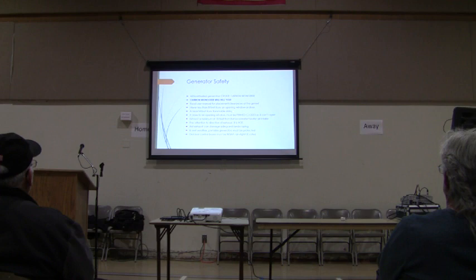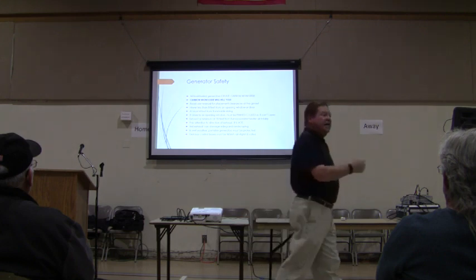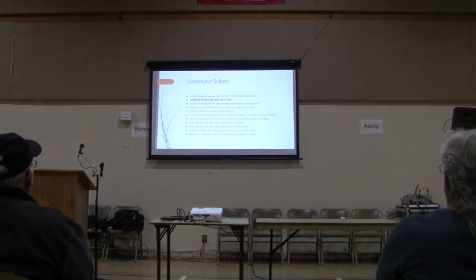Exhaust a minimum of 10 feet from furnace and water heater air intakes. And I would say 10 feet from an outdoor unit as well, because the combustion byproducts will destroy the wiring in an outdoor condensing unit. I've seen it. It's very acidic. Exhaust 10 feet from furnace and water heater intakes, so that you're not pulling in the combustion byproducts instead of oxygen or air into the appliance. It interferes with the combustion process of that appliance and can clog up the heat exchanger.